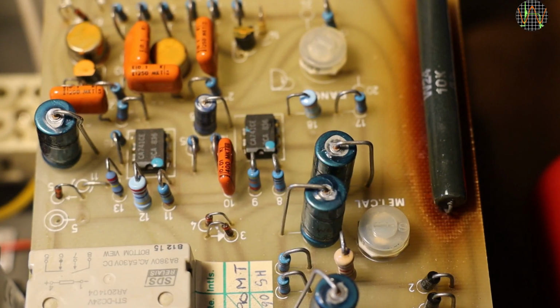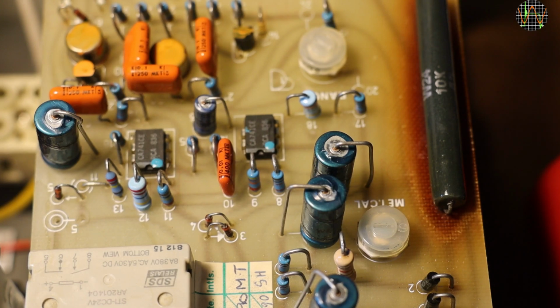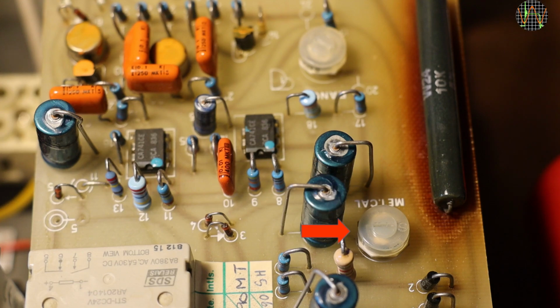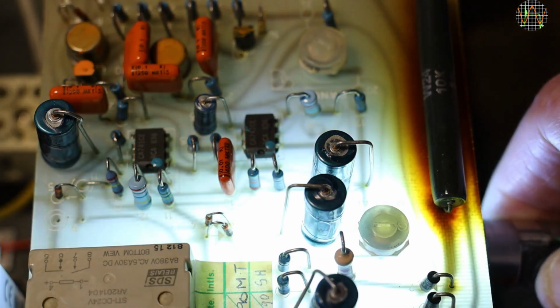There are 4 trim pots in this device, 2 on the PCB above the HV transformer and 2 on this one. Each PCB contains a trim pot labeled METCAL, meter calibration. I suspect this is the one for the current/resistance meter, but first I want to record the way this pot is currently set. In case it's the wrong one, I can restore the setting. The best way is to measure its resistance, of course, with the power off. It is very tricky to get to the legs of the pot directly, so I have a look where the traces go to find a more convenient spot to probe.